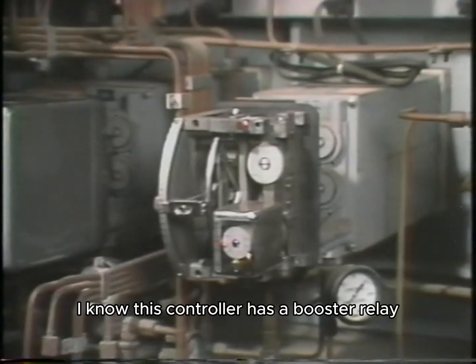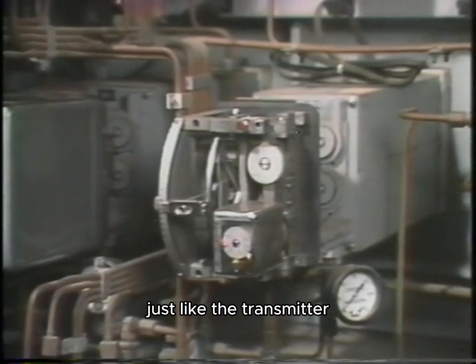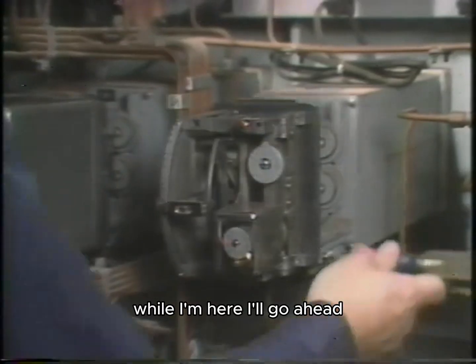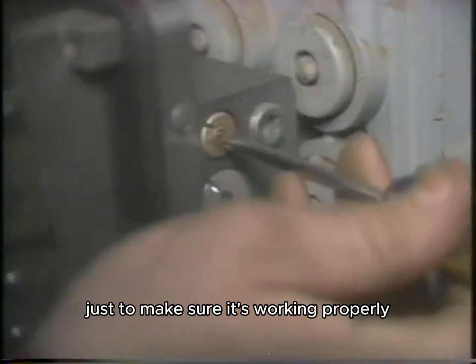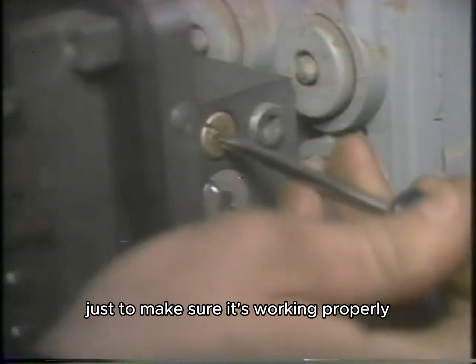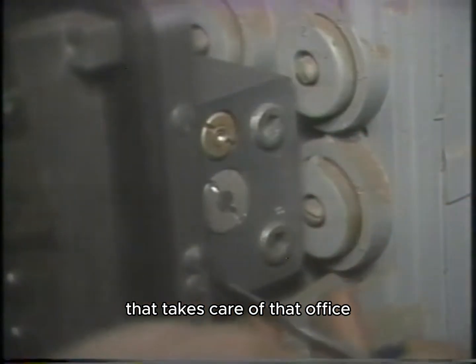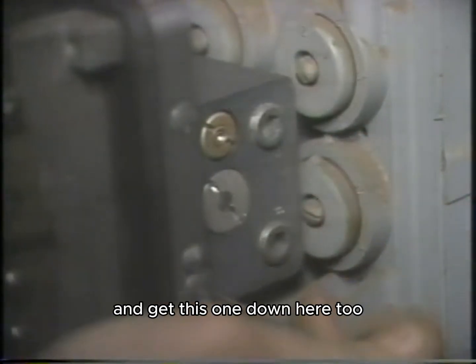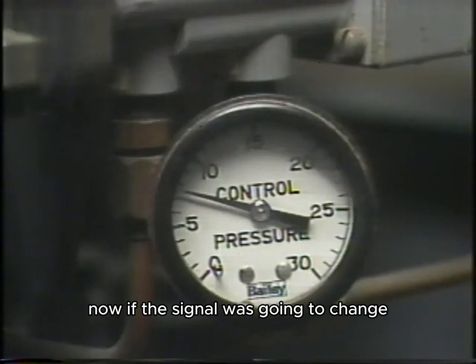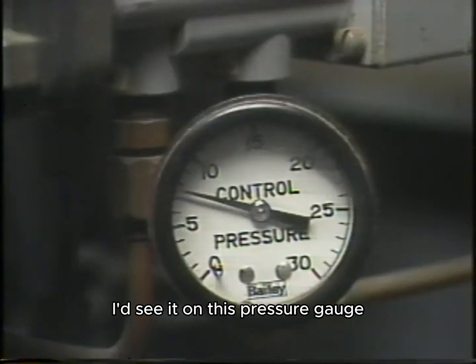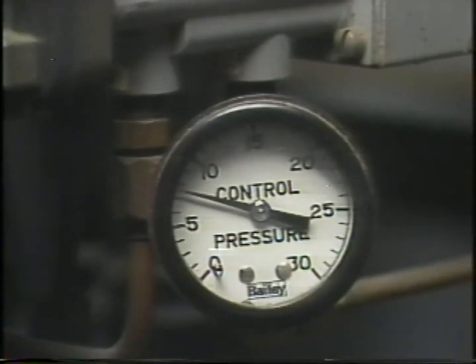I know this controller has a booster relay, just like the transmitter. While I'm here, I'll go ahead and punch the relay out, just to make sure it's working properly. That takes care of that orifice. I can get this one down here too. Now if the signal was going to change, I'd see it on this pressure gauge, but it's staying the same.